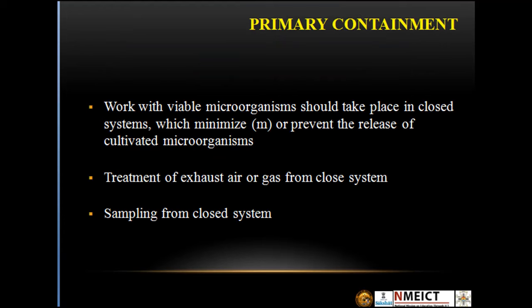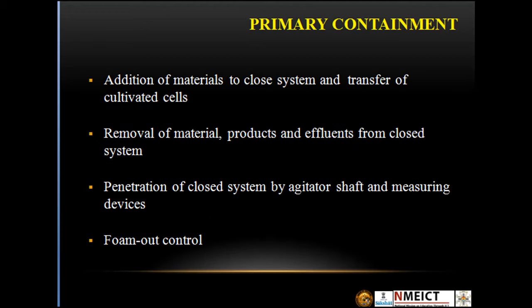Regarding primary containment: work with viable microorganisms should take place in a closed system to minimize or prevent the release of cultivated microorganisms. Key considerations include treatment of exhaust air or gas from the closed system and sampling from it; addition of material to the closed system and transfer of cultivated cells; removal of material, products, and effluent from the closed system; and penetration of the closed system by agitator shafts or measuring devices and foam-out control.